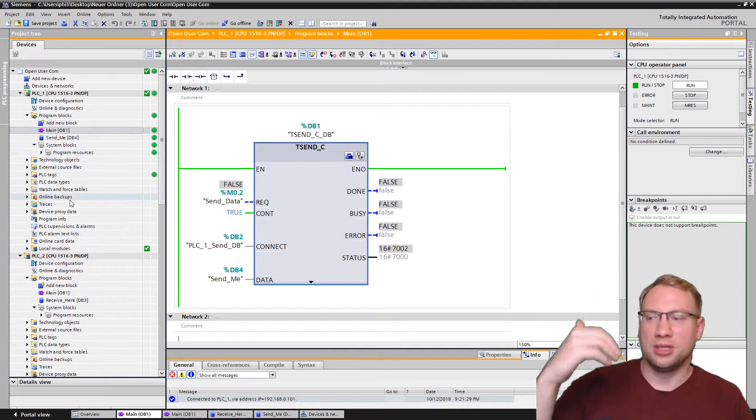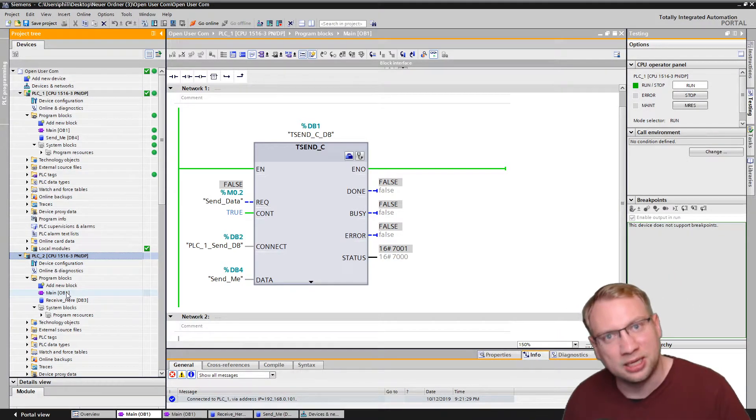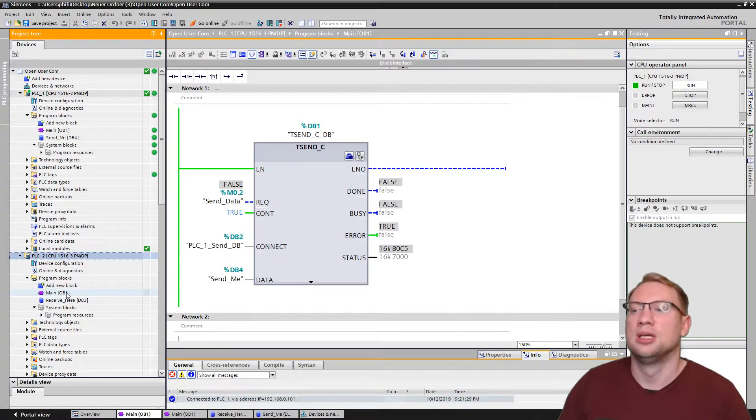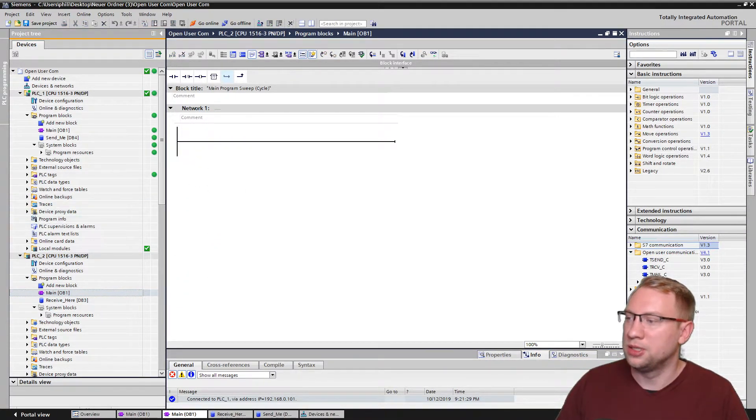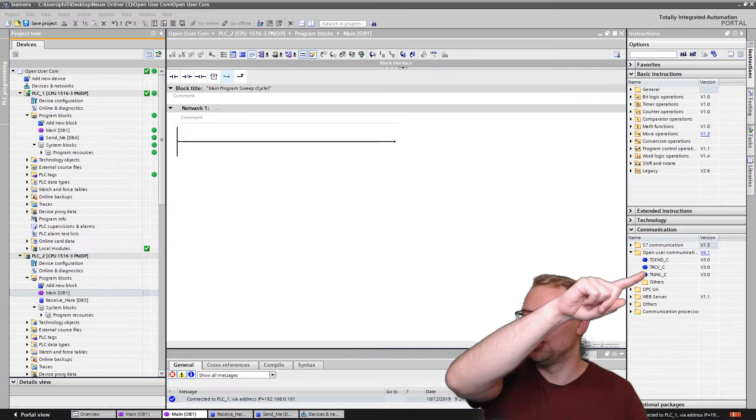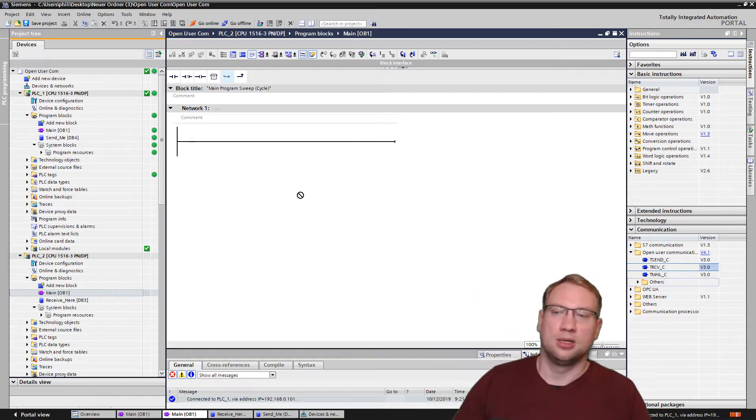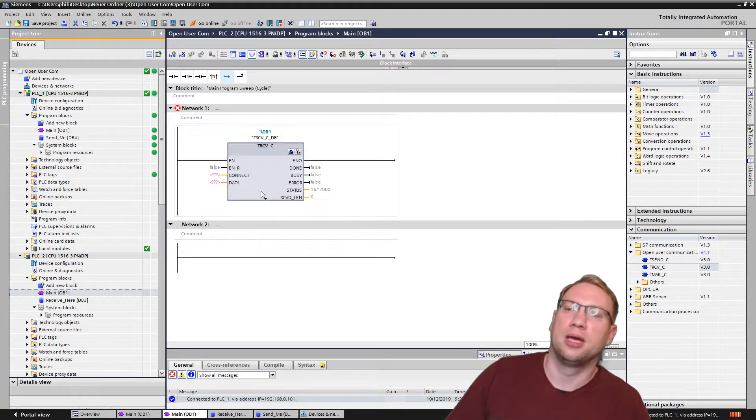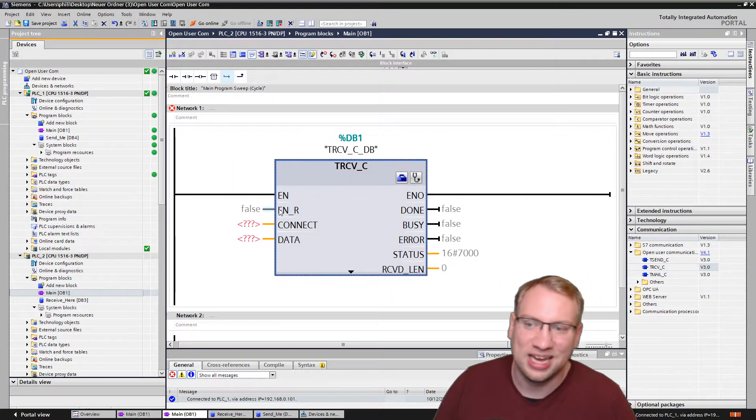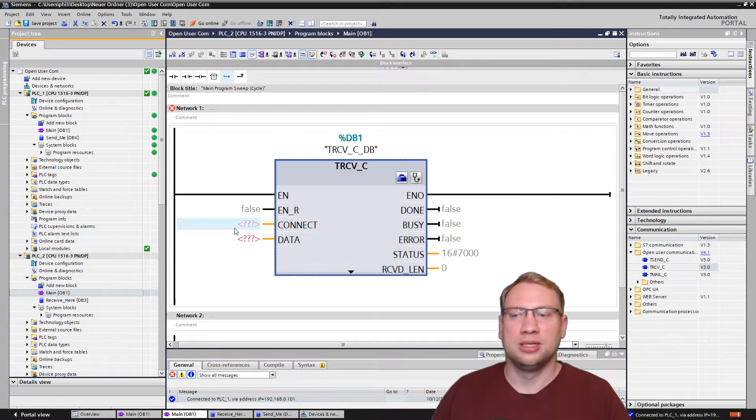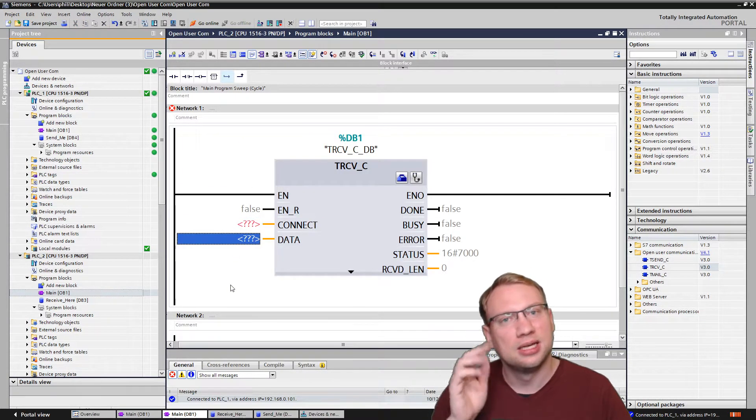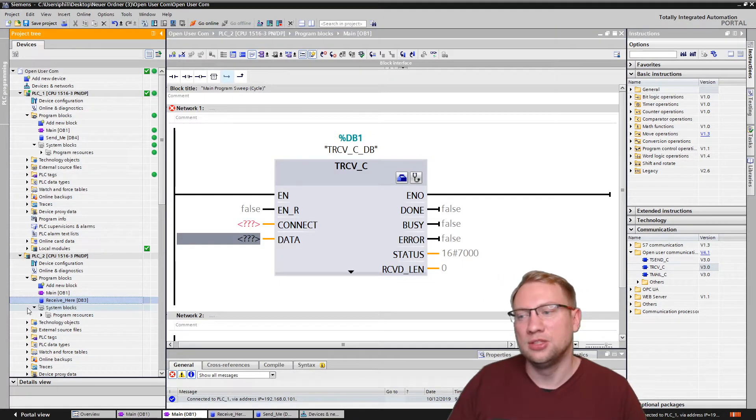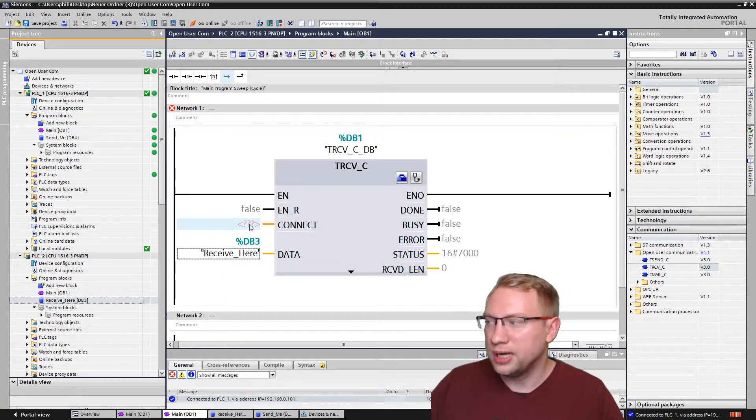Now for the second PLC here, we don't want the TSEND. Make a guess, one PLC sends, the other one receives. We need here in the other program, we need open user communication, the TRECEIVE. I put it in here. It needs an instance data block. I hit okay, and look at this. It looks very similar. It needs an enable. When do you really want to have the connection? It needs this connect, and it needs data. Make a guess. Data is where are we going to receive the data into. I take receive here. I push it there.